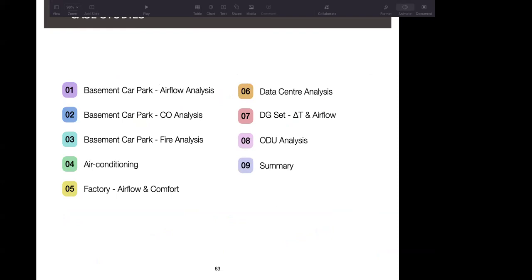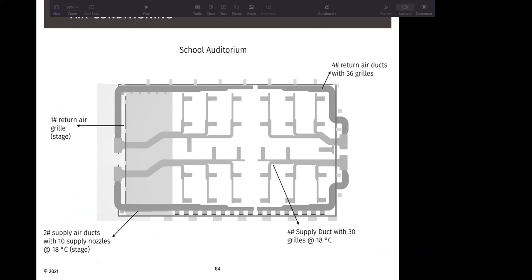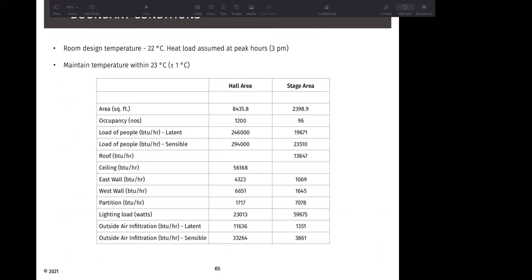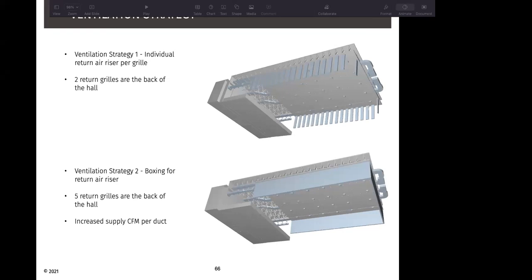Looking at the fourth example of air conditioning, we have a school auditorium with 4 return air ducts and 4 supply ducts to supply air at 18 degrees. And considering this is for air conditioning, we have to look at the heat load data for that particular system. So we have a room design temperature of 22 degrees, and we have to maintain the temperature of 23 degrees plus minus 1. The heat load is assumed at peak hours, and the heat flux has been calculated for people, roof, ceiling, the walls, the partition, lighting load, and any kind of equipment that has been kept in the auditorium. So there were 2 strategies that were studied for this particular problem.